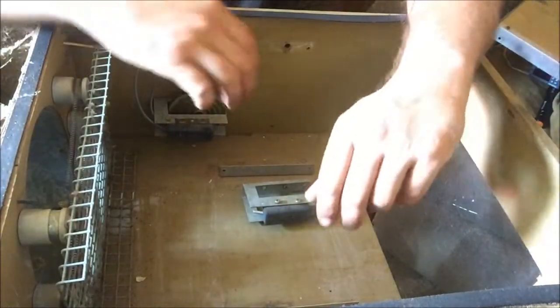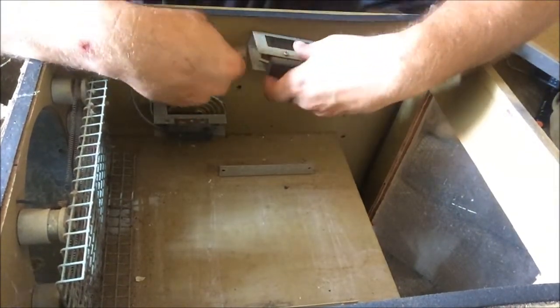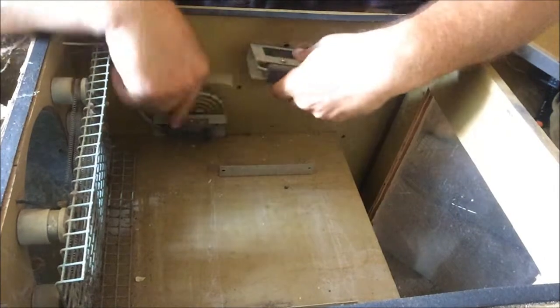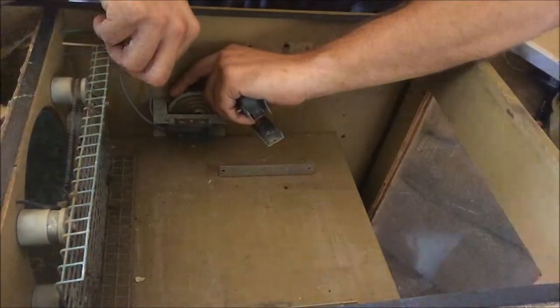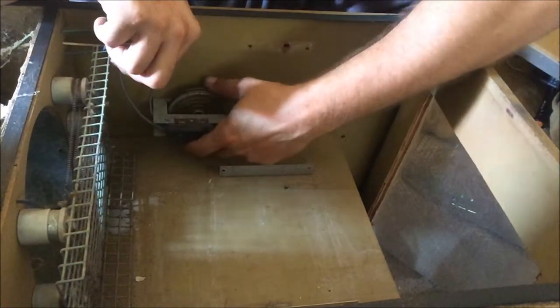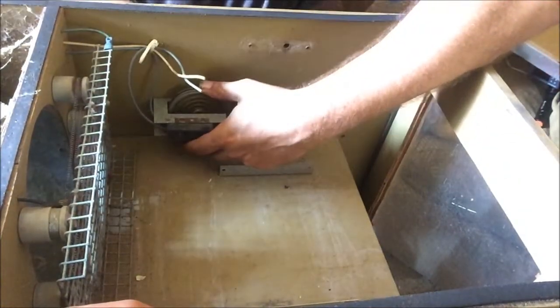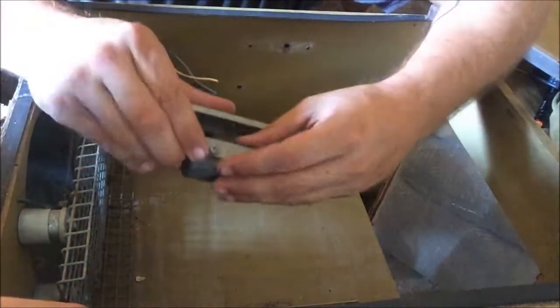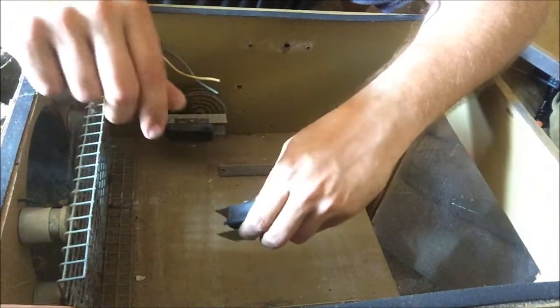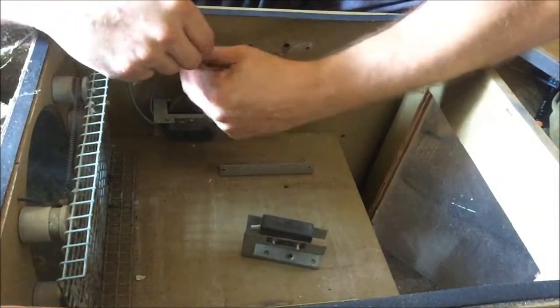Into the top of the incubator. Now this was mounted here and it had a wafer like this coming through it. And as this wafer heats up, it expands and contracts. And that's how it works. And then there's a switch in here that would turn the heating element off and on.